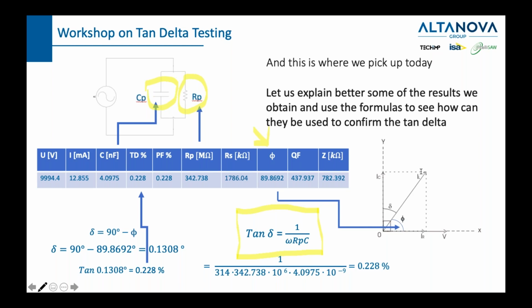If I talk about power transformer, then 1% is okay. But we see that with extra high voltage, sometimes it needs to be much less than 1%. So let's say that 1% is a rough estimate, a conservative one I might even add, but not for all types of transformers. So more or less, that's the thing I wanted to mention.